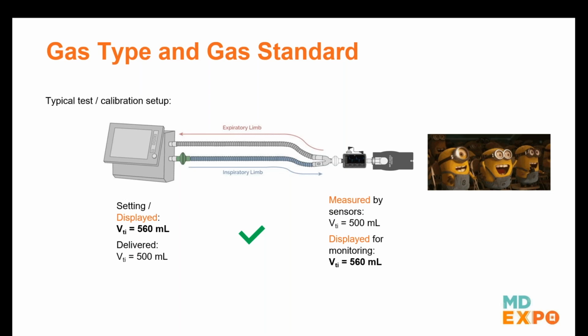Yeah, thank you, Kerwin. That was a great explanation. Again, one of the key takeaways is to really make sure that your gas standard matches the device under test. If there's one thing that you need to remember from today, it's that one. That's so important. Because gas flow analyzers measure all these parameters, they can convert to any gas standard you would ever see on any of the ventilators you're testing. Again, the most frequently used ones are BTPS and maybe STP. So these two you'll see most often.